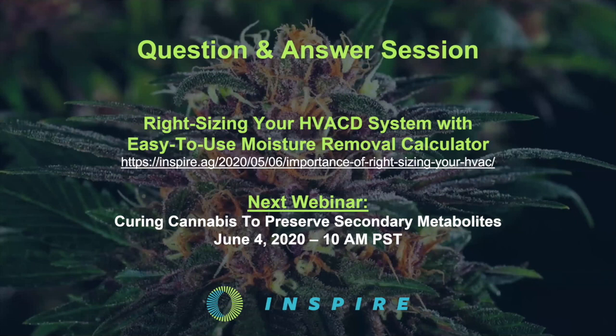We and some other manufacturers in the industry go a step further, and we will move the air from one spot to the other inside the air handling unit, in essence, pre-cooling the air before it hits the cooling coil, and using that same room energy to reheat the air back up. And effectively, we get 30 to 50% less compressor energy out of it. There are other very, very sophisticated ways, including desiccants, to increase the energy efficiency of the whole growing process.